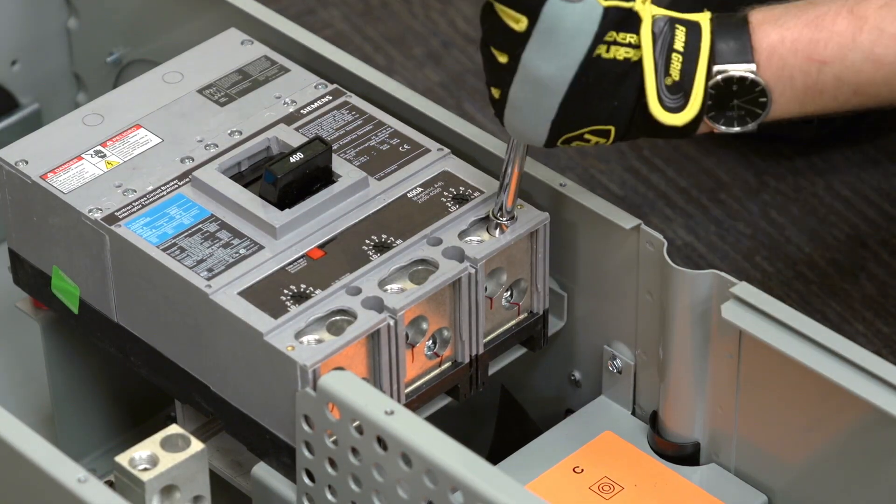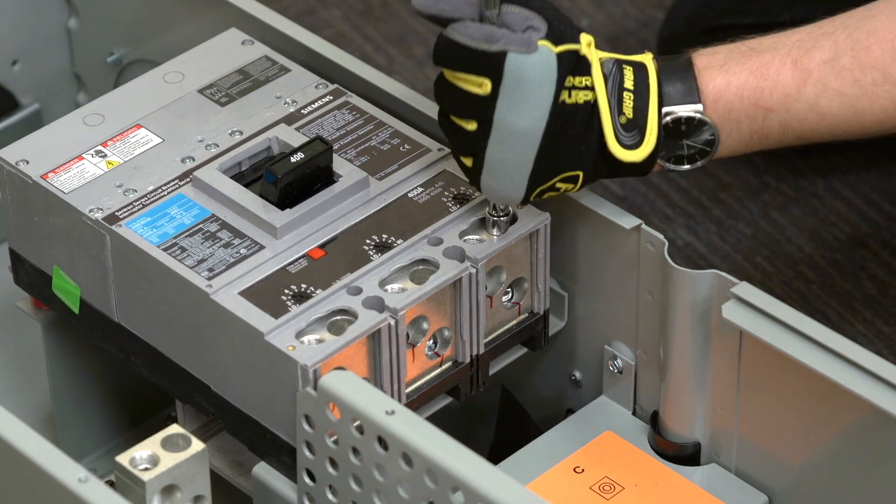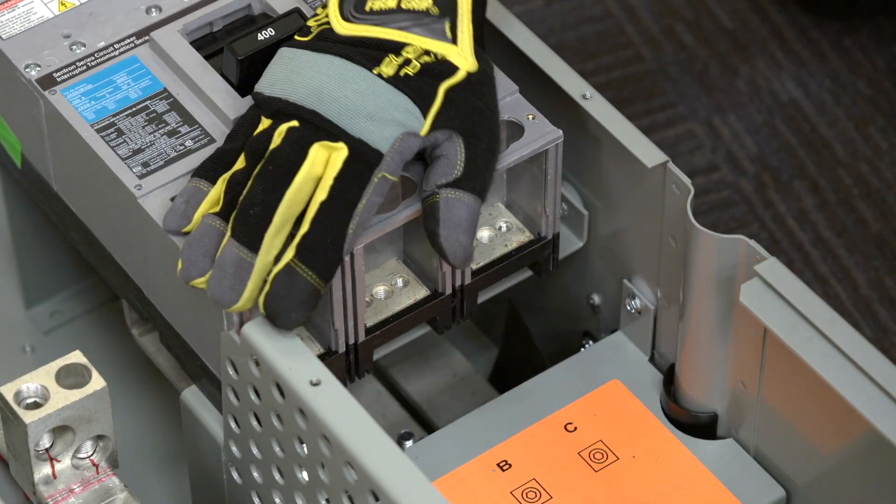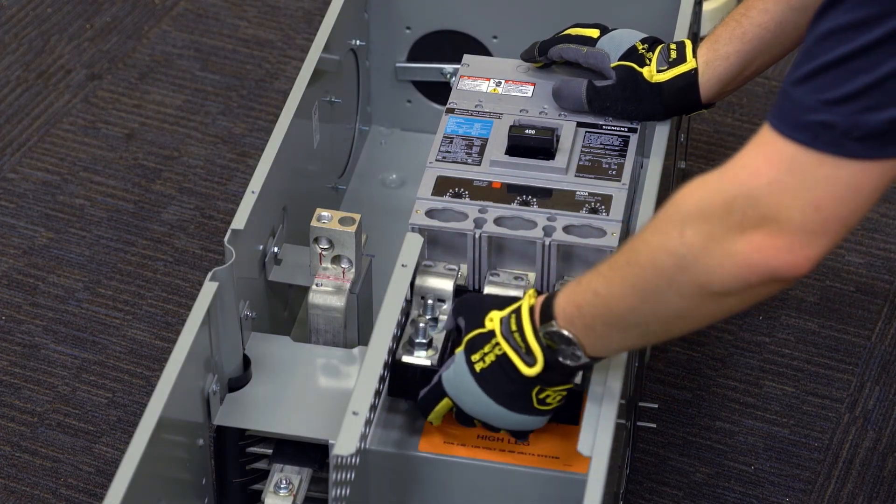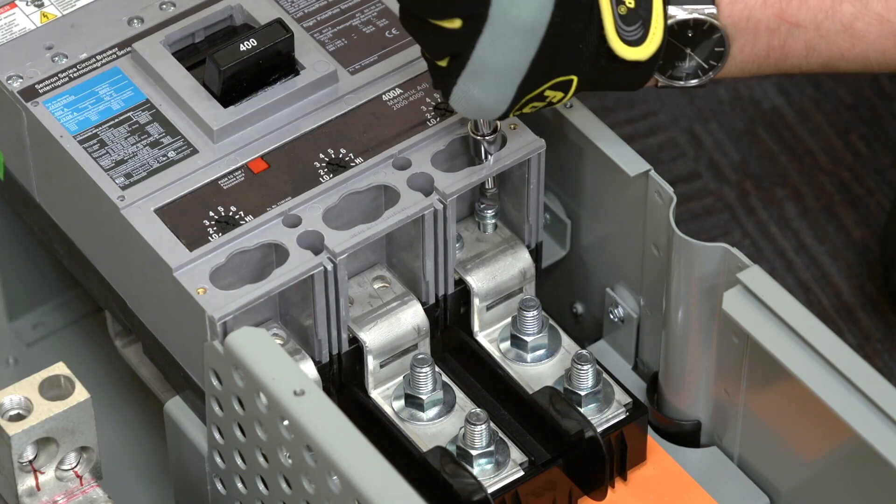One tip to keep in mind when installing a lug landing pad is to perform this installation when the module is lying on its back on a flat surface prior to hanging the module on the wall. This makes unscrewing the tightly torqued screws easier. It may take a strong power tool or a tool with an extended handle to perform this action.